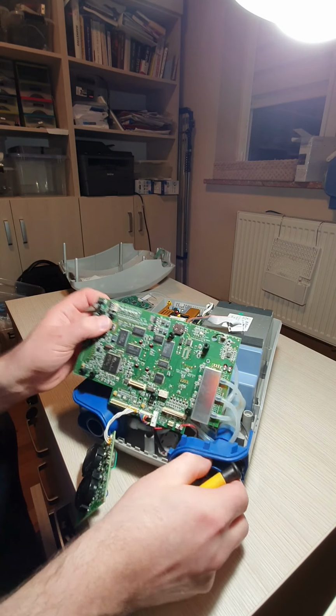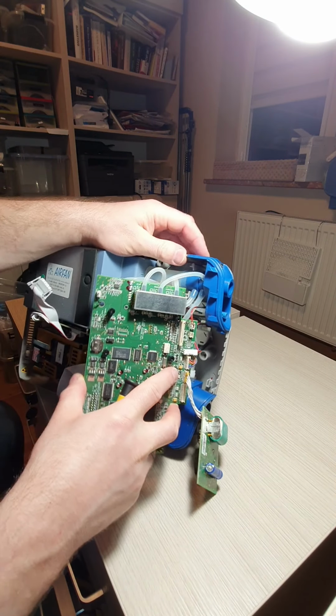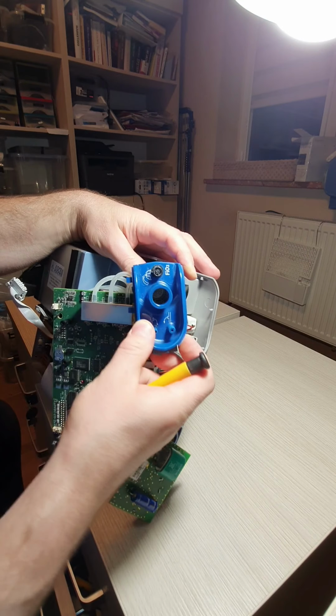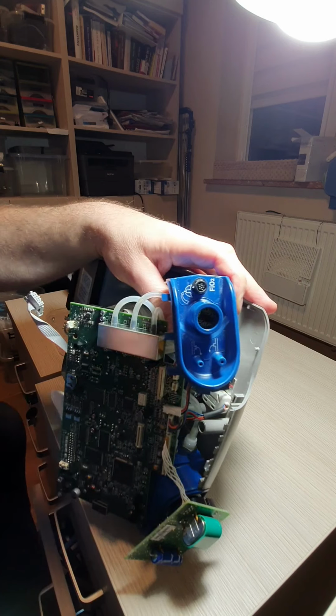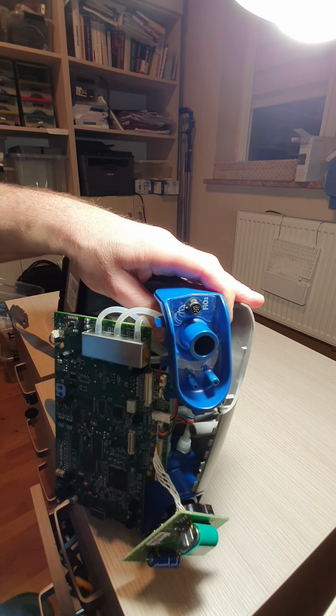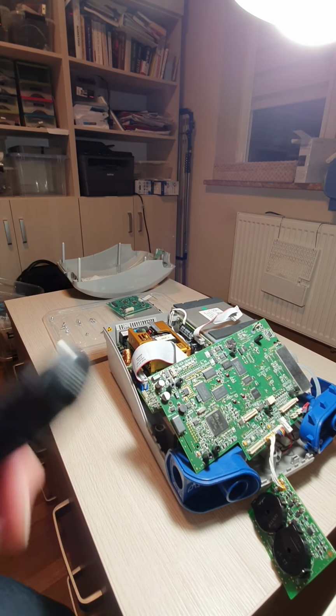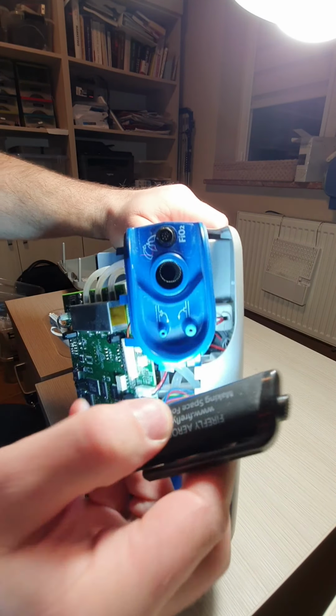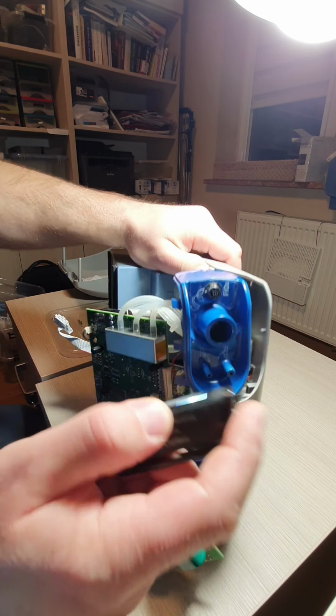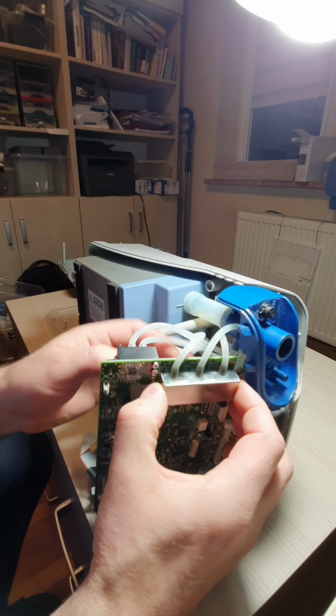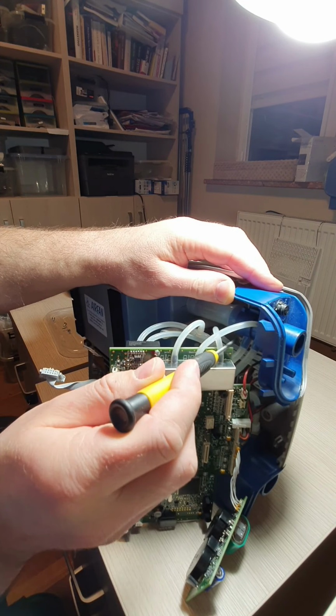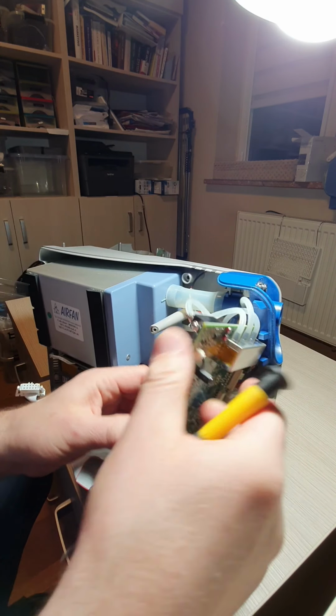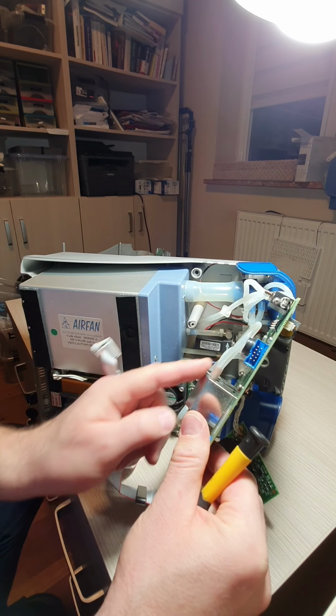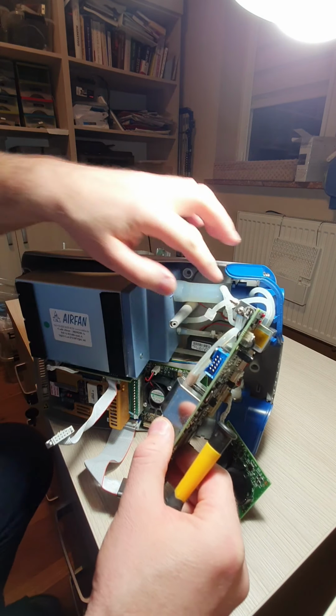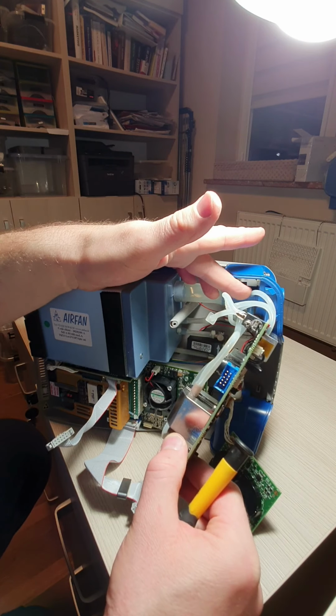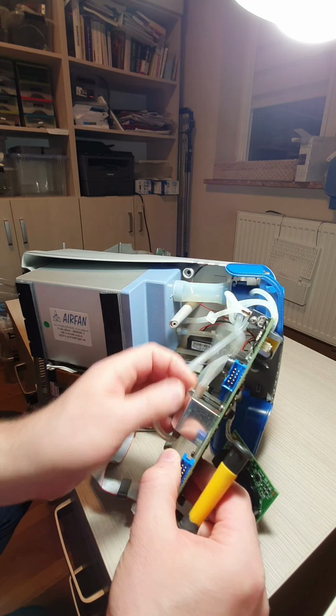So what is interesting in this beast, you can see here, there's some tube. It's empty inside. There is some tiny diaphragm. It's not visible here actually. I can put some additional light on it. Where is the torch? So I found the torch, and you can see here there is a diaphragm inside. There is one tube before the diaphragm. The second tube is after the diaphragm, and they both go to the differential pressure sensor. This is a differential flow sensor, and the diaphragm acts as an obstacle. So the higher the air velocity, the higher the differential pressure that goes through this flow sensor.